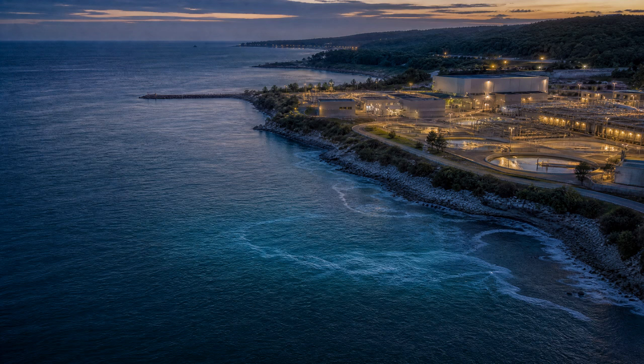A technically mature discussion keeps several questions together. What is the feedwater quality? How does it vary? What pretreatment is required to protect the process? What recovery level is being considered? How does concentration affect scaling and corrosion concerns? How does the resulting brine affect the discharge assessment? And how do these conditions change the energy calculation? These are connected questions because a choice made at one point in the system changes the burden elsewhere.